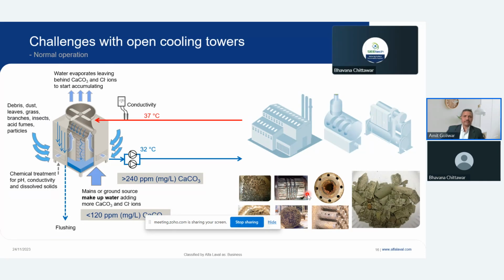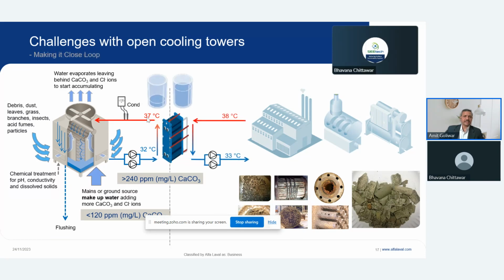So what we propose to the customer is to put a heat exchanger in between, a more efficient heat exchanger which can work at a 1 degree approach. And if you have a 1 degree approach, you can make a closed circuit for the water which is going to the process, and the highly contaminated water can remain close to the cooling tower. By doing that, I know that my process is not going to be hampered by higher TDS. So I can even increase the level of TDS. I can reduce flushing, I may even reduce chemical treatment, and I may reduce the makeup water.